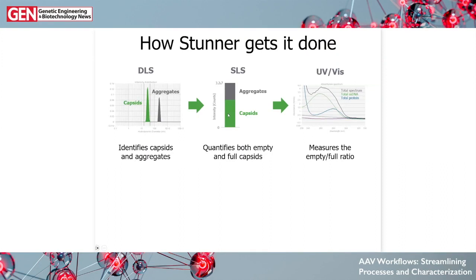What Stunner does step by step: first, DLS identifies the capsids, the aggregates, and how intense the signal is from each population — say the area under the curve in green is 70% of the total. That info then helps split up your SLS intensity signal from a total value into the amount attributable just from your capsids — 70% of the total area. Finally, UV-Vis brings in info about empty/full ratio and total amounts of protein and DNA in mg/mL or ng/μL, which are then combined automatically to get you an accurate capsid titer.